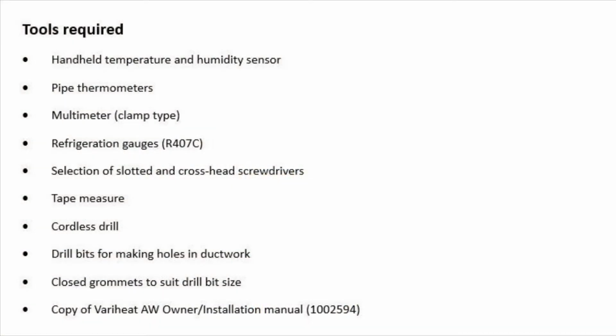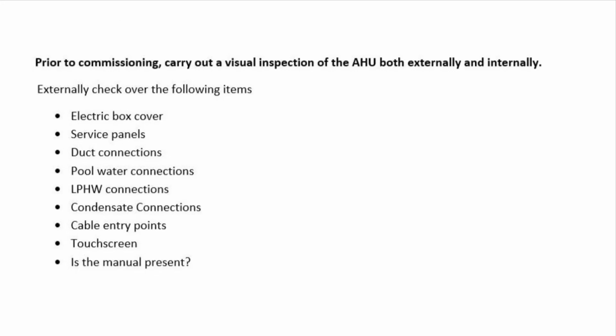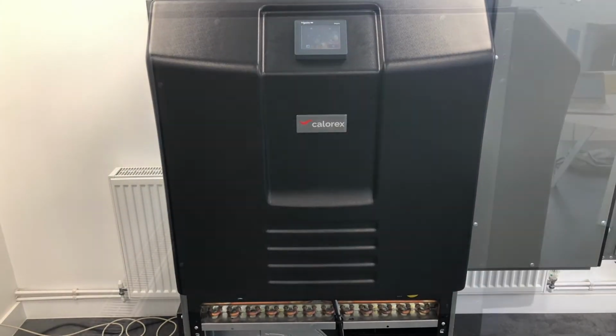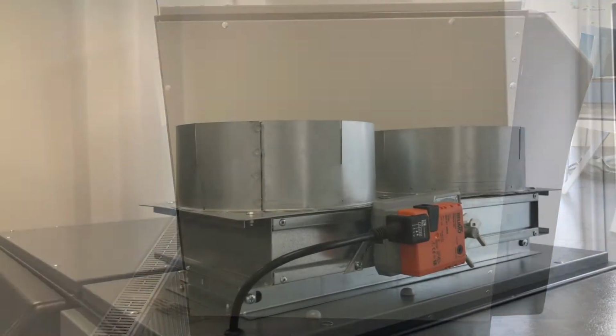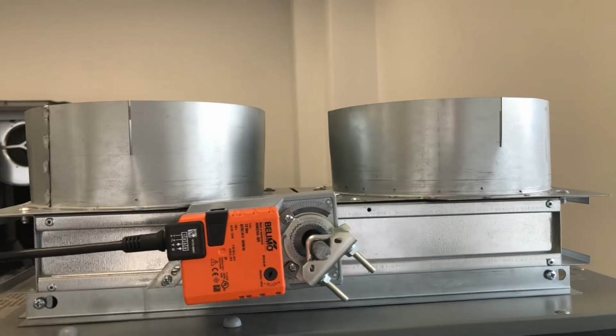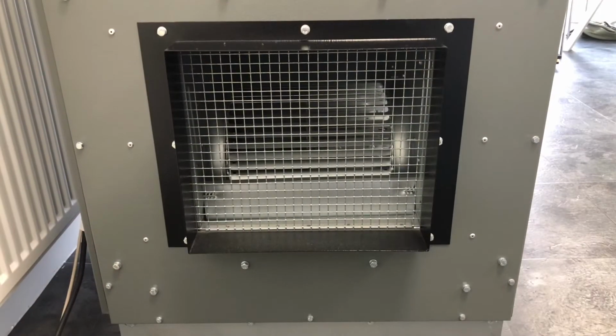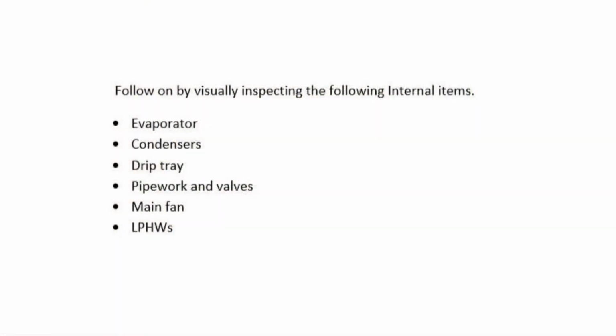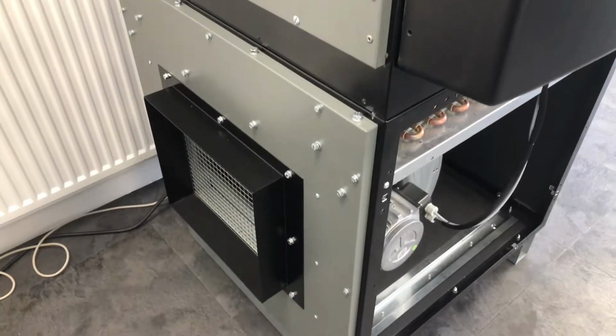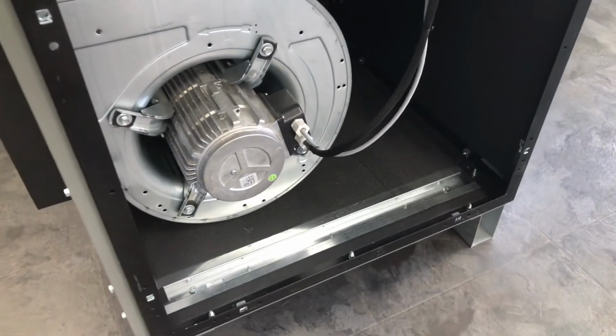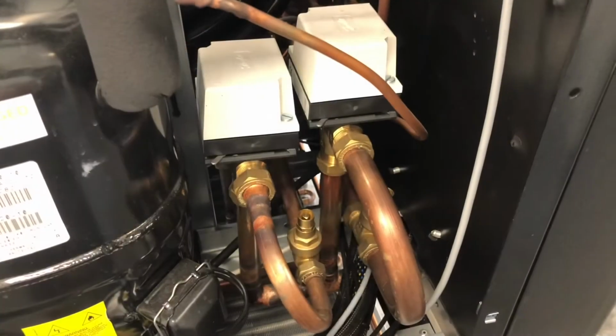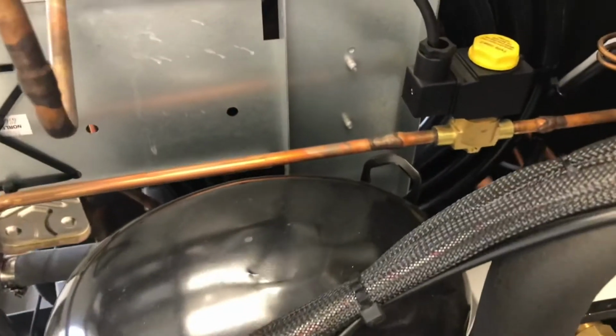As an engineer, it is paramount that you are also prepared, ensuring that you have the tools to hand to commission the AHU. To begin commissioning, carry out a visual inspection of the AHU externally and internally. The external inspection will allow opportunity to ensure the installation is complete, report any transport or installation damage, and ensure that full access is available for future works such as maintenance and repair. Again, inspect the unit internally to ensure the installation is complete and that no damage has occurred. In both instances, take photographs as evidence.